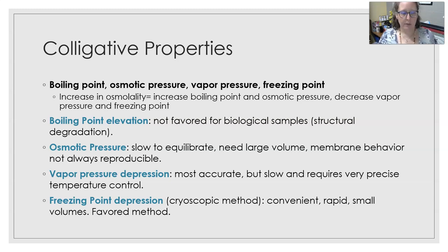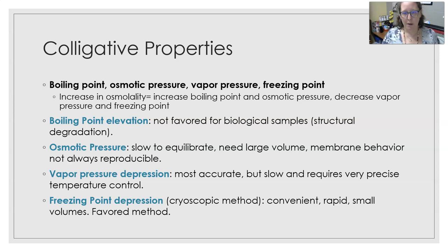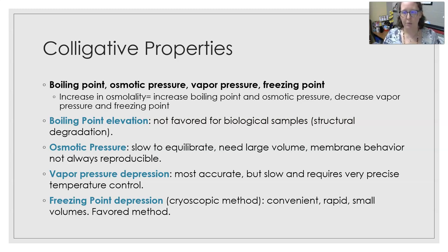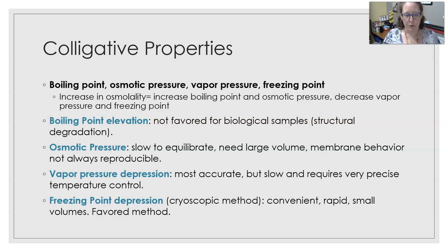So why did we settle on freezing point depression? Boiling point elevation was not favored for biological samples because you get structural degradation — as you boil a sample, you destroy all the proteins. Osmotic pressure is slow to equilibrate, requires large volumes, and membrane behavior is not always reproducible, so it's more prone to errors. Vapor pressure depression is the most accurate, but it is slow and requires very precise temperature control. Freezing point depression, also known as the cryoscopic method, is convenient, rapid, and only requires small volumes — therefore, that's the favorite method.